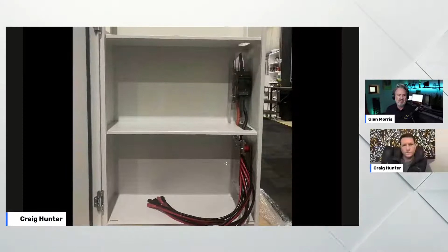Yeah, so I can see you were talking about those new plastic screens. The circuit breaker in the top section there, we've done some Perspex shrouds to go around the circuit breaker, so there's no touch points, fully insulated for the consumer to use as their main DC isolator. With the no-arc breakers, they don't come with an enclosure, or it's very hard to find one that fits around them, so we've made them up with the Perspex.